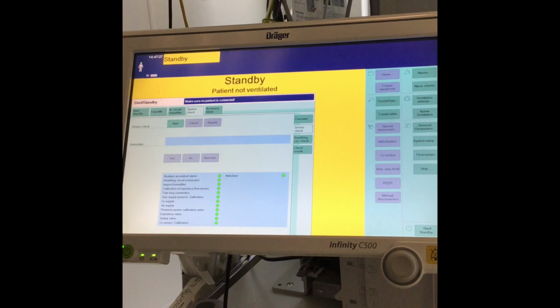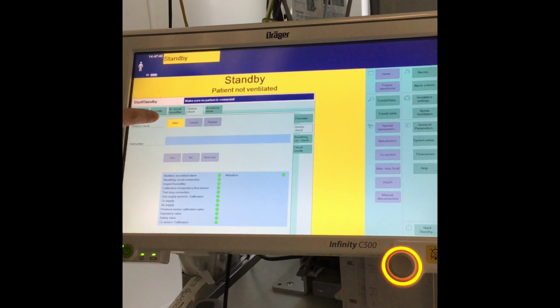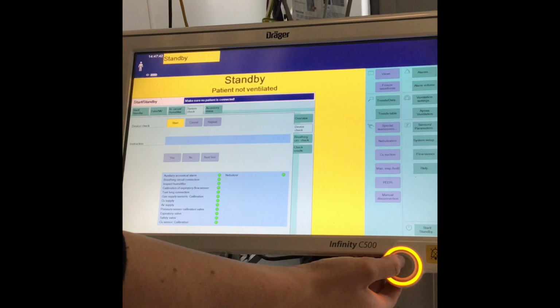This should be done before patient use, and if the ventilator has been disconnected from the oxygen inlets and moved into a different bed space, it should really be put through another check. So what we're going to do is just going to start. So we'll hit start and we're going to confirm that by pushing the dial in.